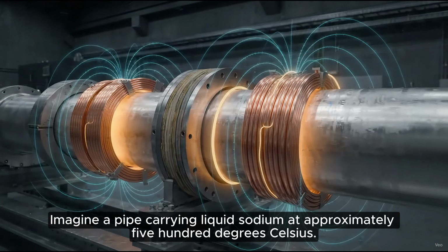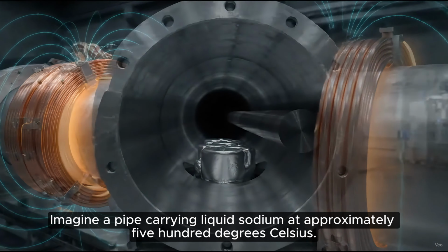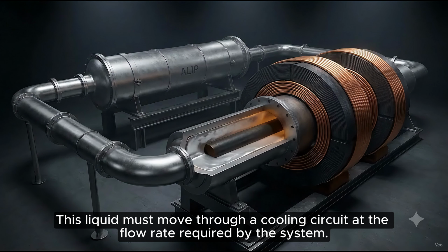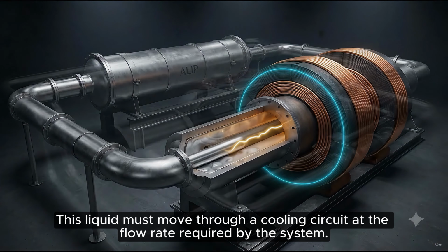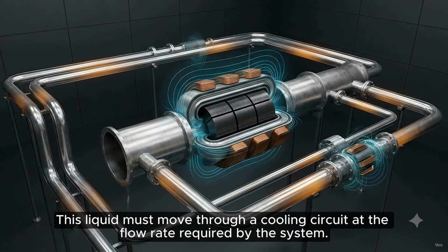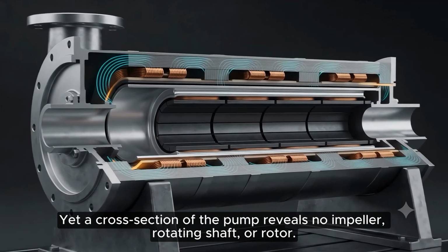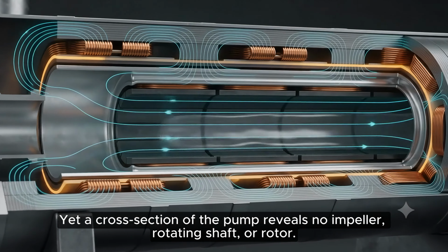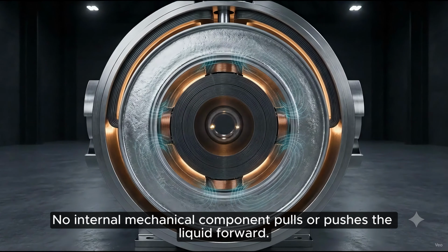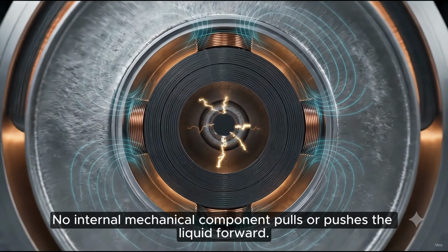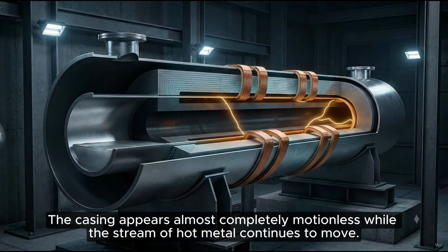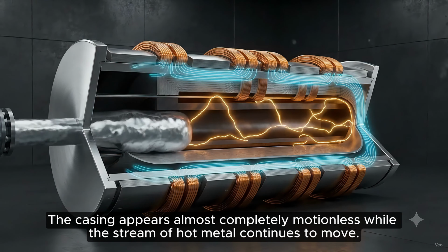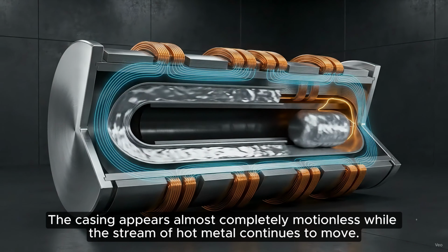Imagine a pipe carrying liquid sodium at approximately 500 degrees Celsius. This liquid must move through a cooling circuit at the flow rate required by the system. Yet a cross-section of the pump reveals no impeller, rotating shaft, or rotor. No internal mechanical component pulls or pushes the liquid forward. The casing appears almost completely motionless while the stream of hot metal continues to move.